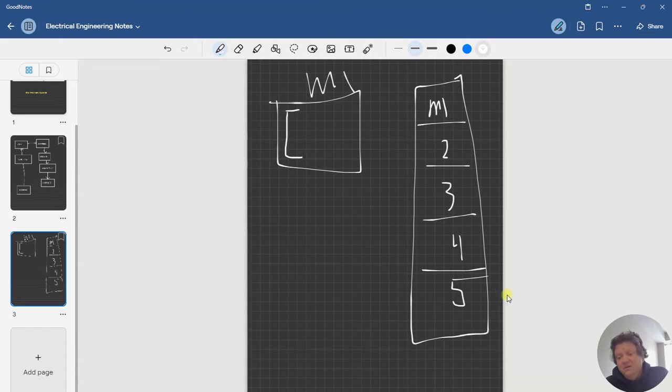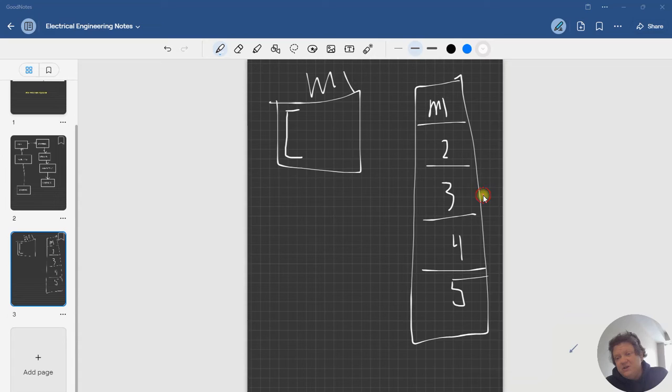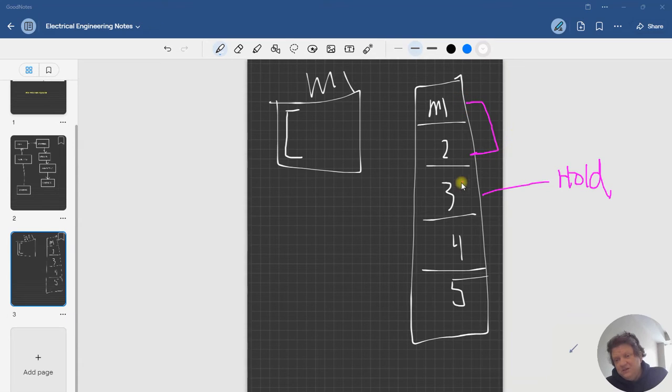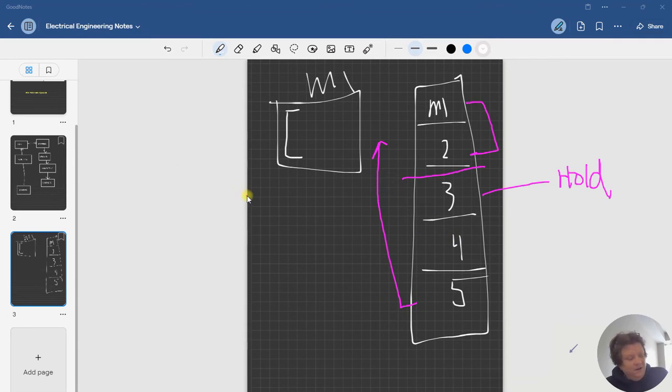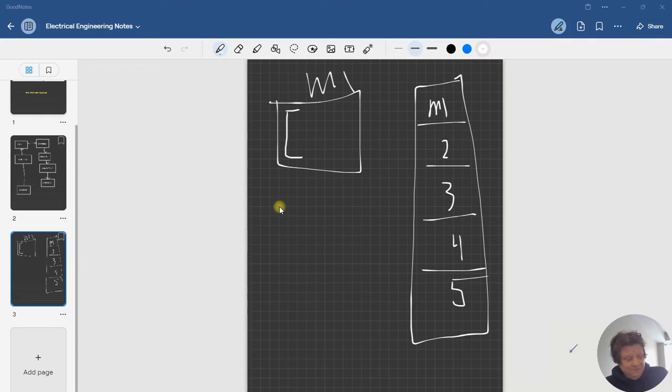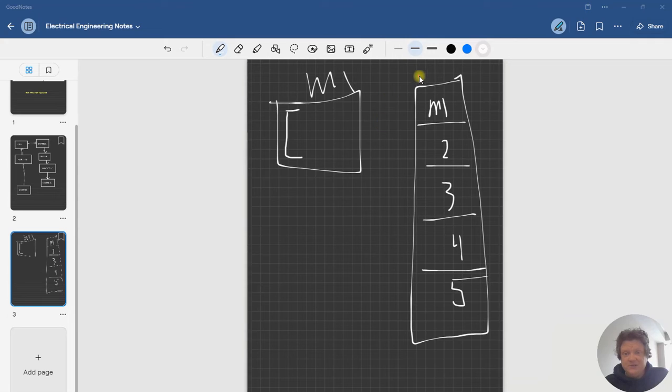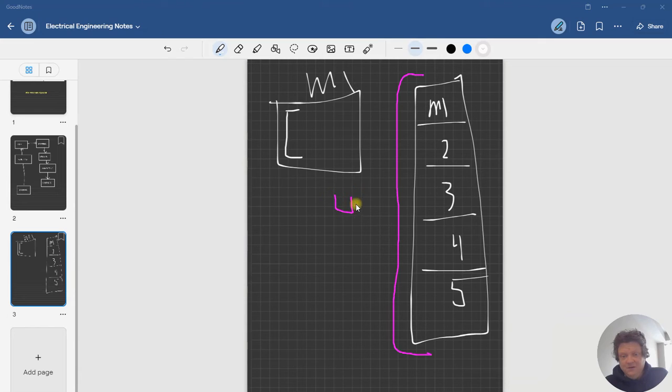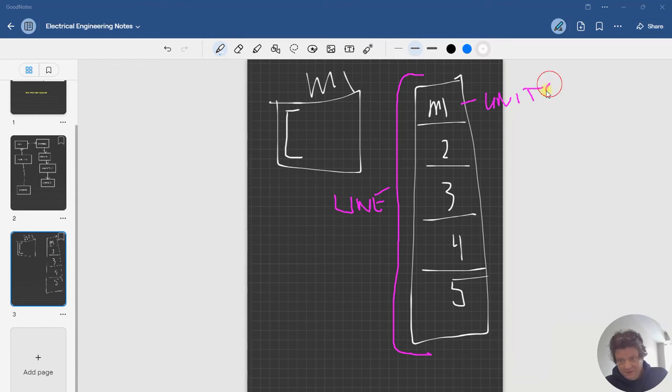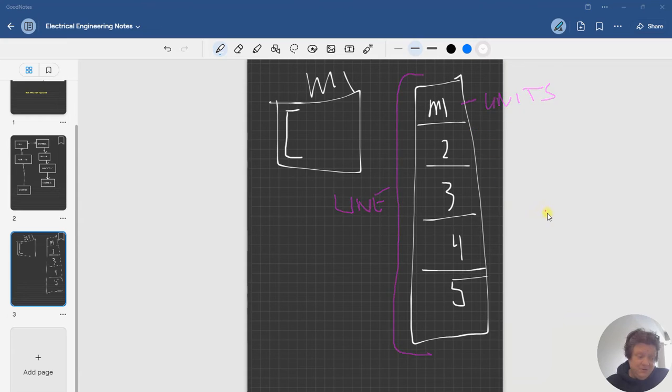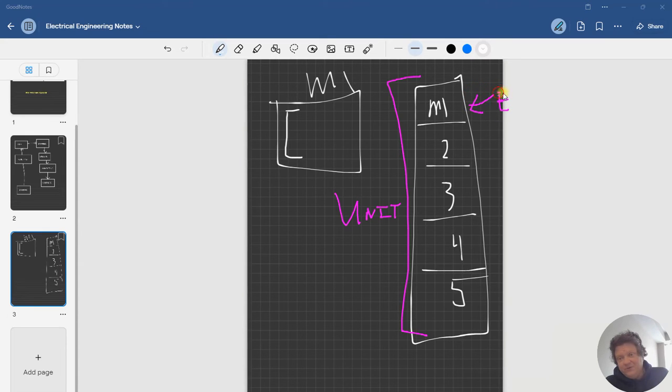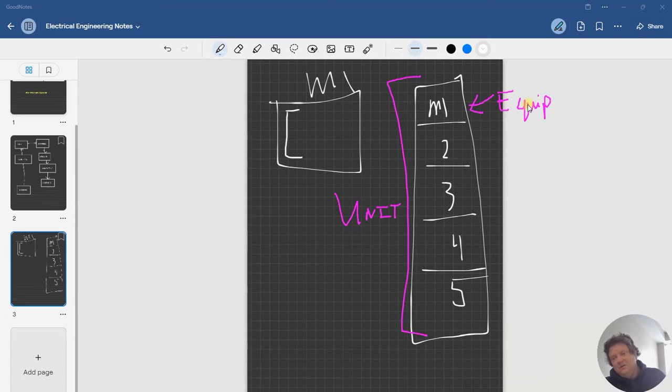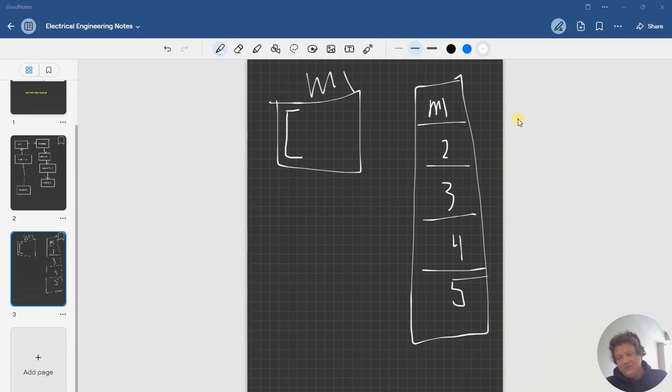But if you come over here and you got your machines right, say machine three goes into a holding pattern because he's waiting on machine one and two to finish. These guys have to communicate down the line and then it also has to communicate back that way. That's why PackML has overlying structures. There would be a framework for the whole line and then you call these units or machines. Actually they call this whole thing a unit and then you can break this down to equipment. That's where the creativity can come into because you can name it whatever you got going on. The thing is to create a structure that you can repeat and that you understand within your company and that you can train on well.